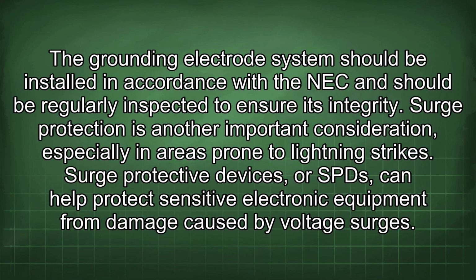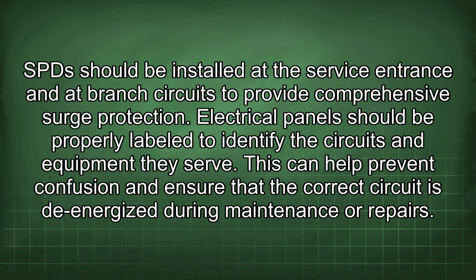Surge protection is another important consideration, especially in areas prone to lightning strikes. Surge protective devices, or SPDs, can help protect sensitive electronic equipment from damage caused by voltage surges. SPDs should be installed at the service entrance and the branch circuits to provide comprehensive surge protection.